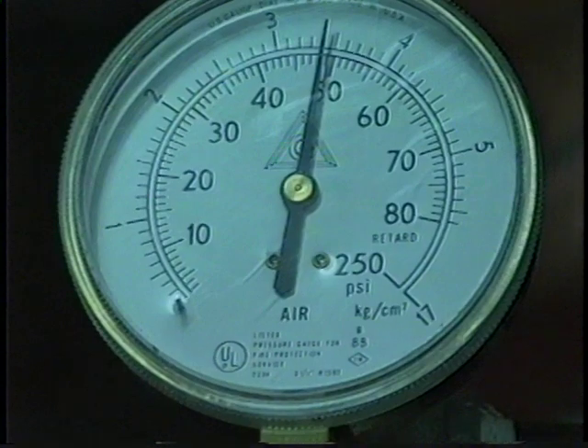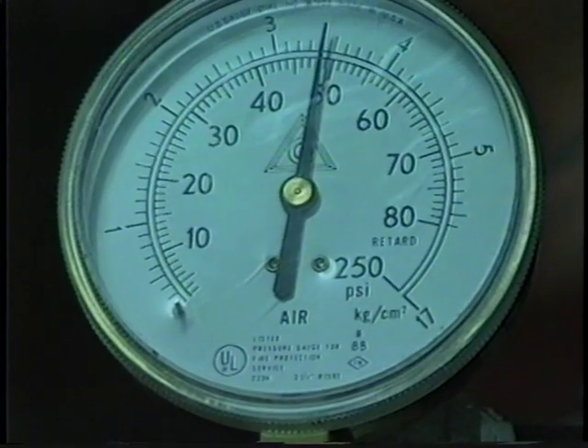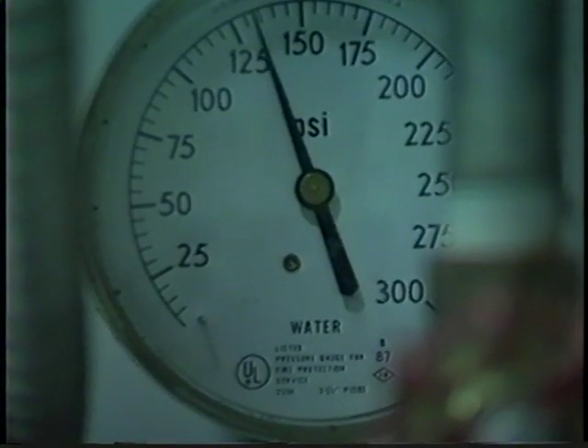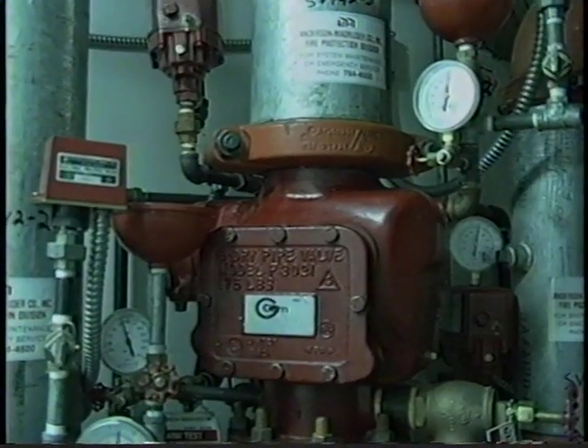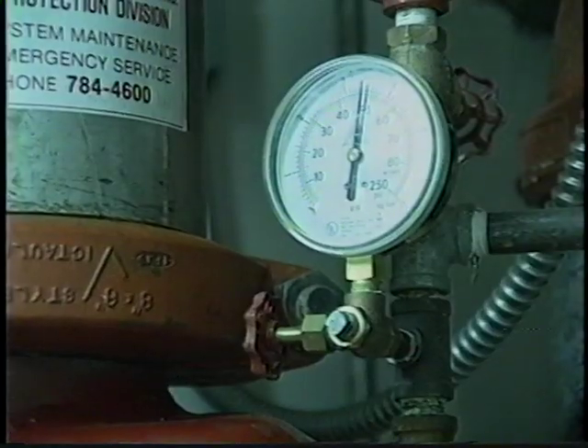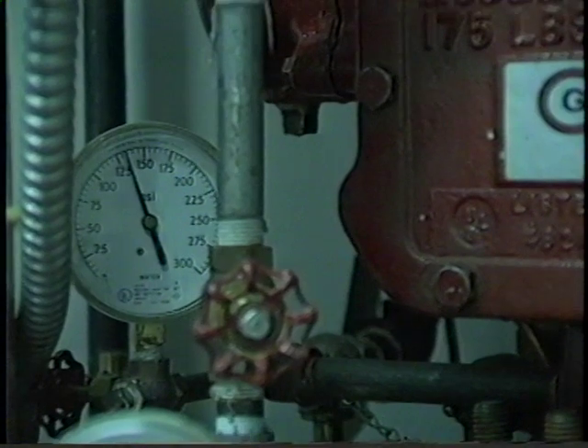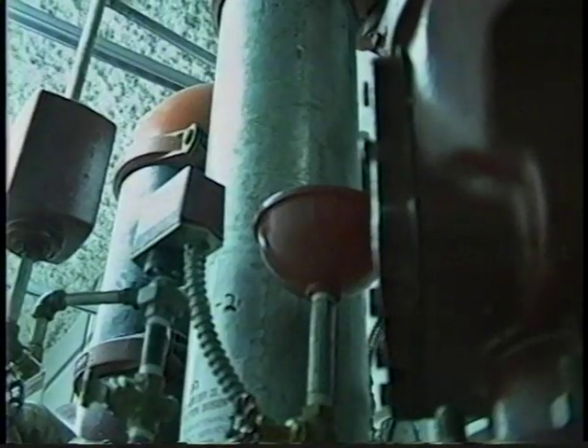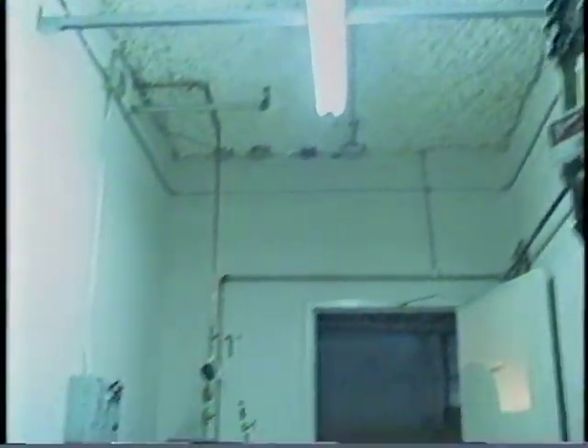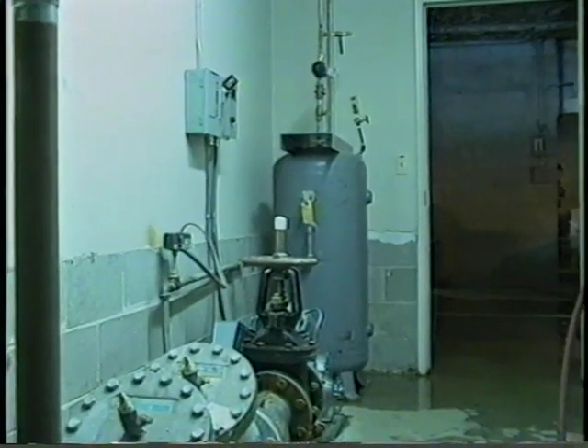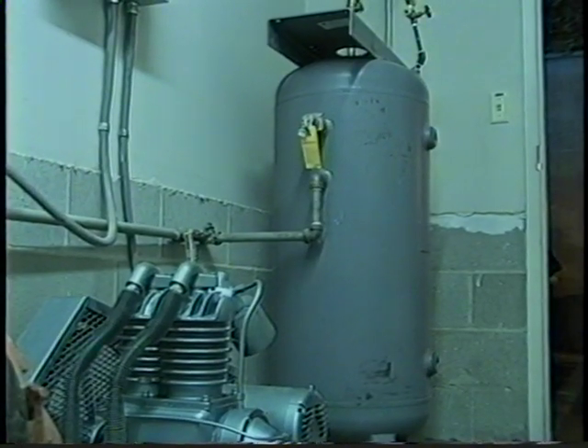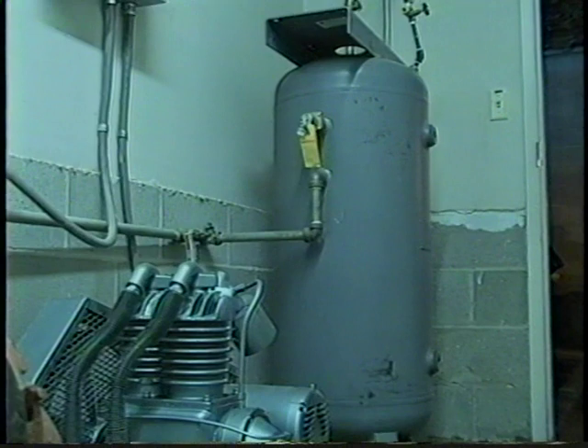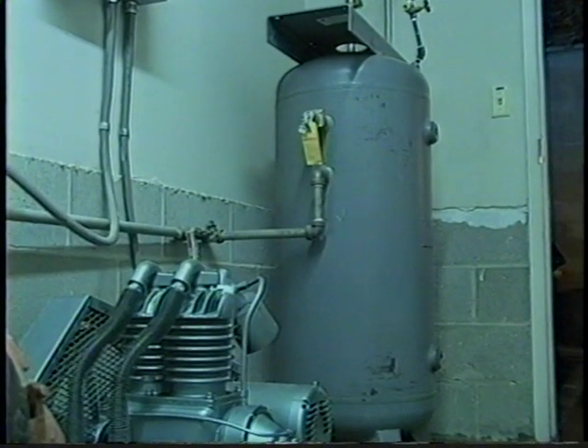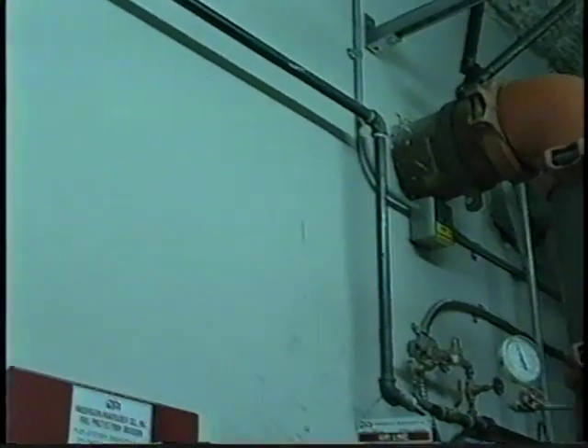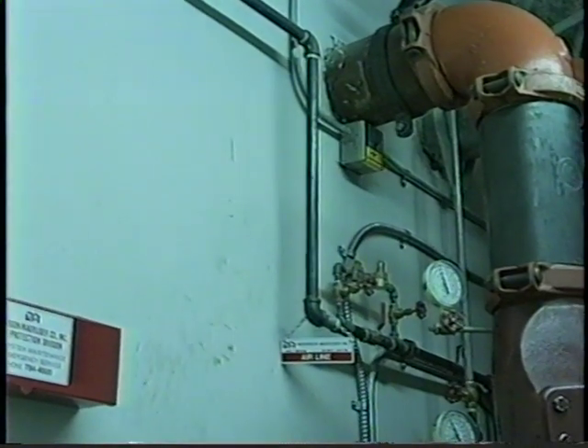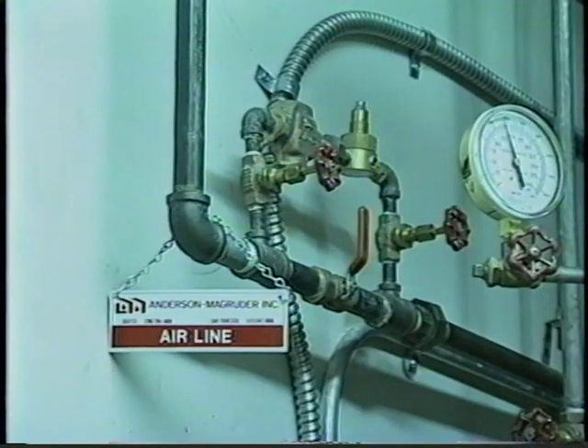Normally, the air pressure gauge should read substantially lower than the water pressure gauge. If the two gauges read the same, this system has been tripped and water has entered the pipes. The air pressure for a dry system may come from either a plant air service or from an air compressor and tank used exclusively for the sprinkler system. In a large dry pipe system, it may take several minutes for all of the air to be expelled from the pipes.